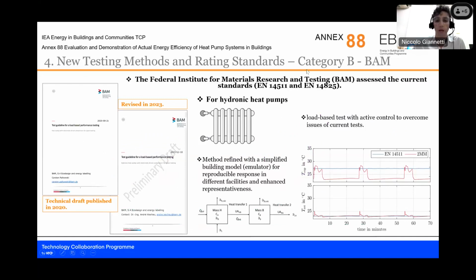Then, as I mentioned before, the BAM, the Federal Institute for Material and Research and Testing in Germany, review current standards in Europe, EN 14511 and EN 14825 for hydronic heat pumps, and also adopted a method that is load-based test to test the unit when operated with its own built-in control or native control. Recently, they republished, revised the methodology with a new draft that introduces the virtual model of the building and the inertia coming from the pipelines of the hydraulic system. And results are being reported, confirming enhanced representativeness and enhanced reproducibility of the result.